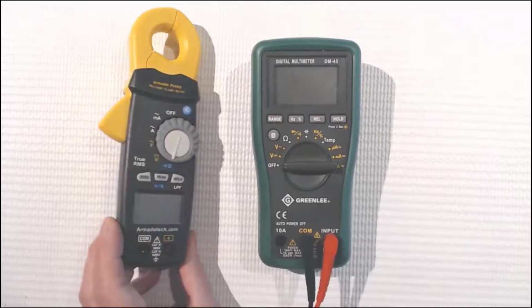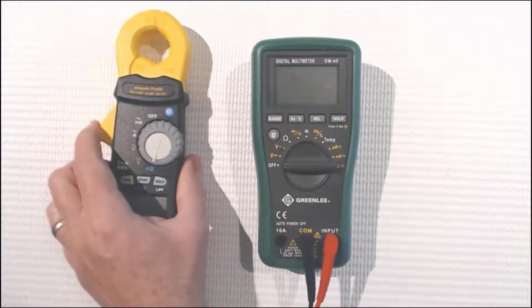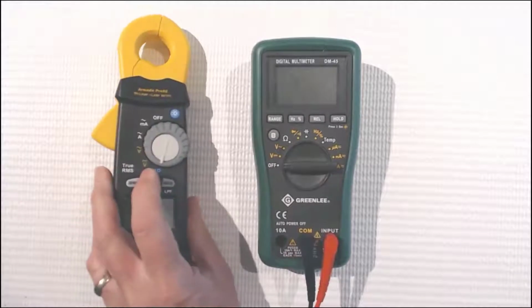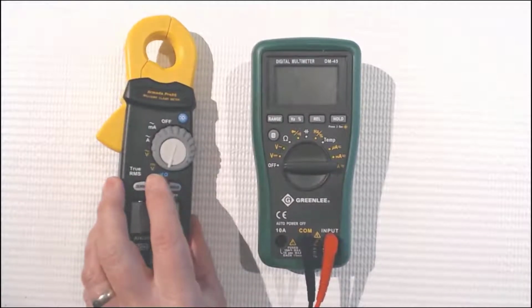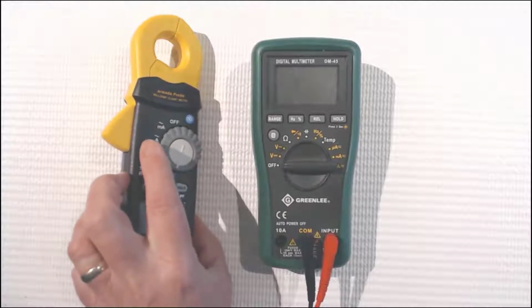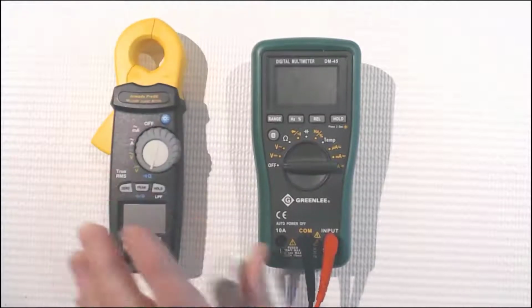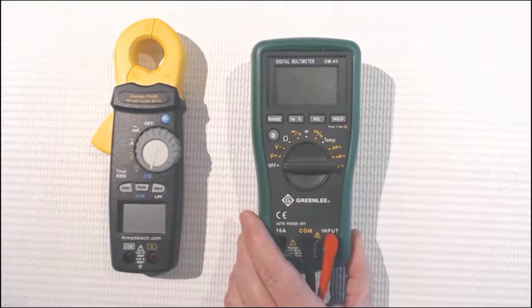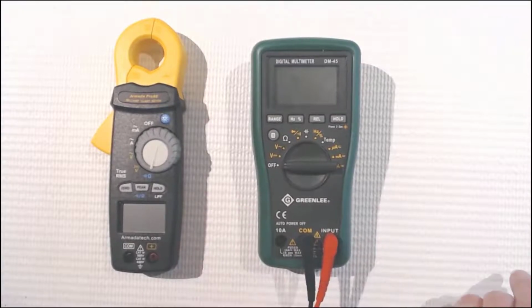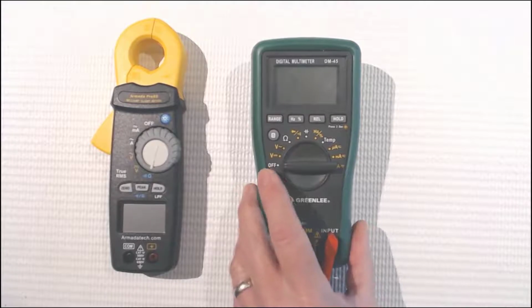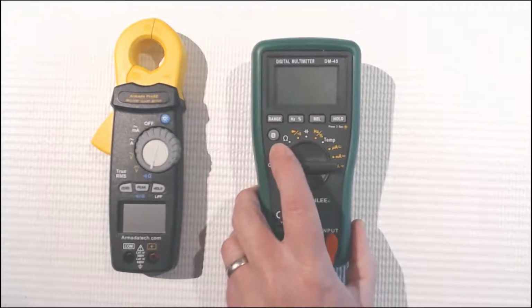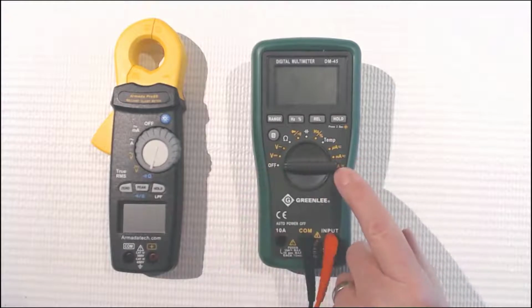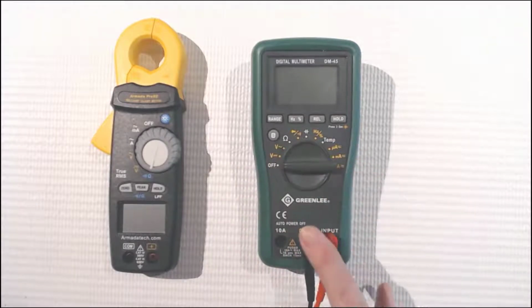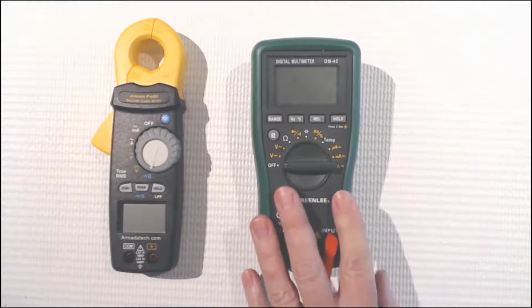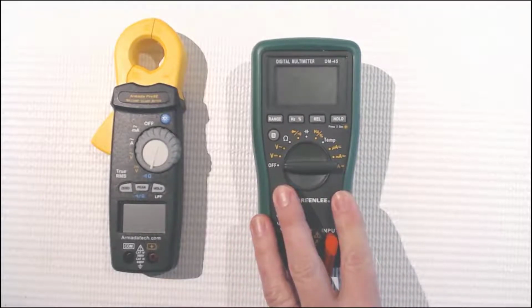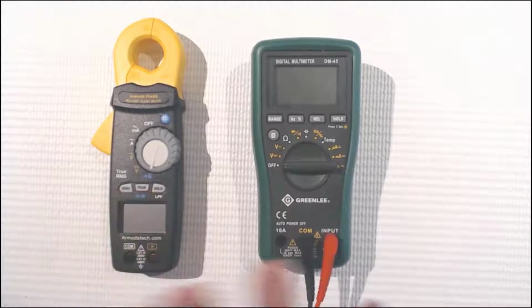This first device is a milliamp clamp. It's got the clamp portion in here, and it's got a dial. And on the dial, we have resistance, voltage for DC and AC, AC amps, milliamps, and off. On a volt ohm meter or a multimeter, it's the same difference. We've got voltage for AC and DC, resistance, a diode check, and if you add additional sensors, you can do other things. So the big difference is this one will not work for amperage checking. This will work for amperage. So that's the biggest difference.